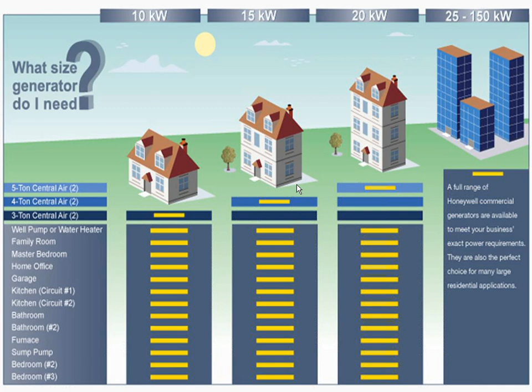So this is Generac's sizing guide. I bring this up only because every once in a while I run into a homeowner who says, Generac said I can use an 8 kW. I said, well, you've got a 4-ton air conditioner, so you really need a 15 kW. We're looking at almost double what you thought. So just be aware that this is readily available. People will use it to get an idea of what they're at, and you might come in and tell them something completely different. If you run into critical applications or hospitals, give me a call. We have lots of software available to help size that kind of stuff.